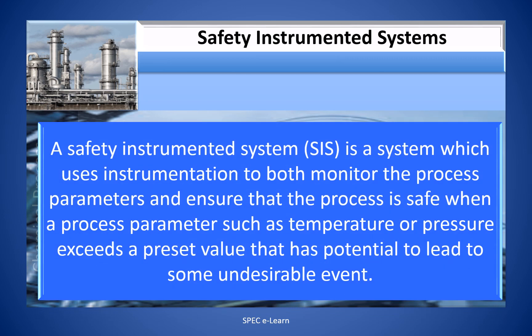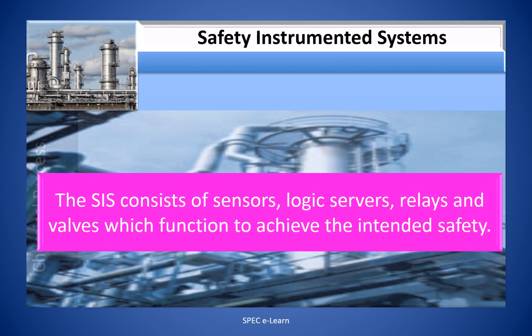A Safety Instrumented System uses instrumentation to both monitor process parameters and ensure that the process is safe when a parameter such as temperature or pressure exceeds a preset value that has potential to lead to some undesirable event. The SIS consists of sensors, logic solvers, relays, and valves which function together to achieve the intended safety.